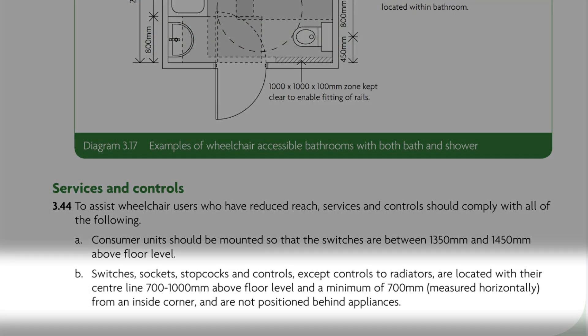Category three dwellings change the rules even more and require that switches and sockets are mounted with their centre line 700 to 1000 millimetres above floor level, and be no closer than 700mm from an inside corner.